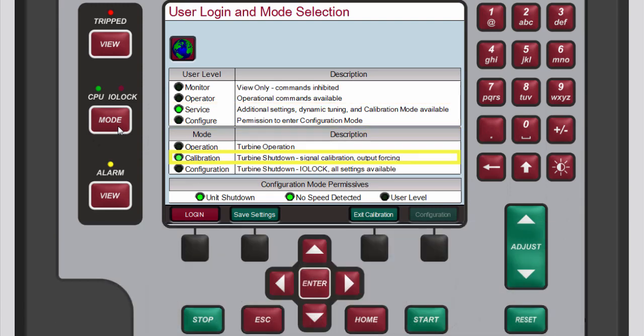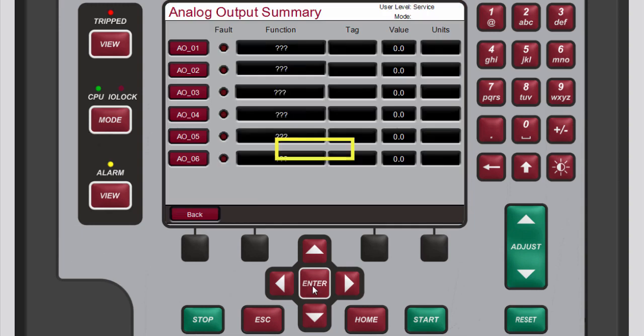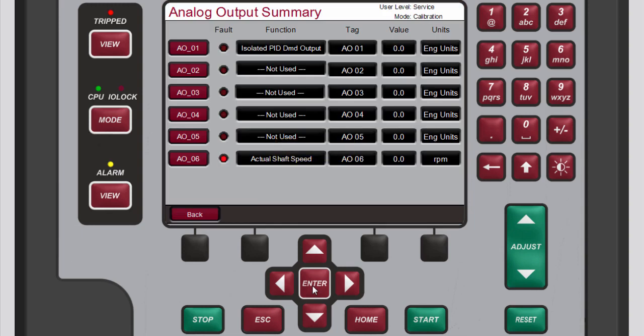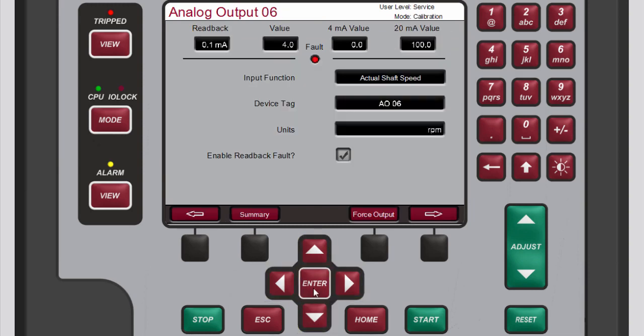Once the controller is in calibration mode, return to the home screen. Then navigate back to the analog output summary screen. Use the navigation cross keys to highlight any of the analog output channels and then press enter. Now that you are in calibration mode, a new force output button has been added to the menu bar. Forcing analog output values allows you to verify that the end device is reacting correctly to the signal it is receiving across the full range of values.